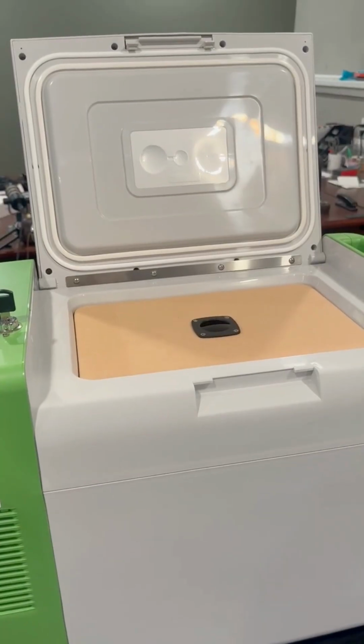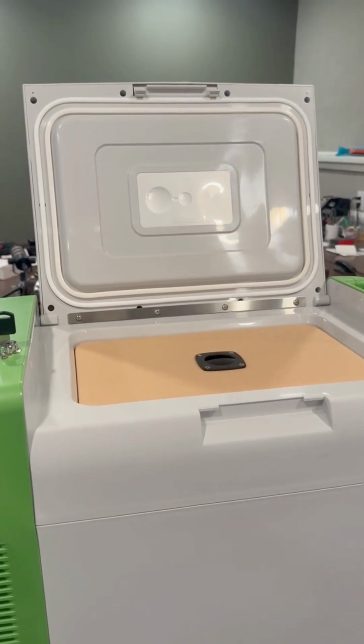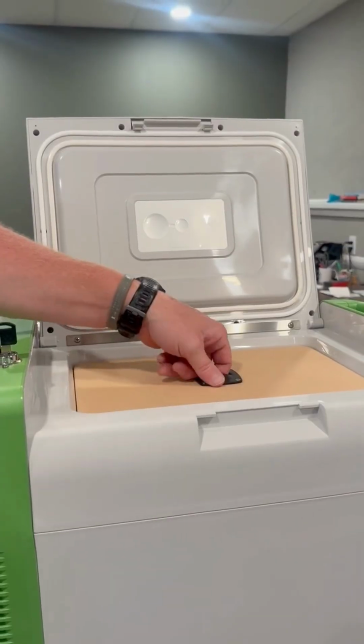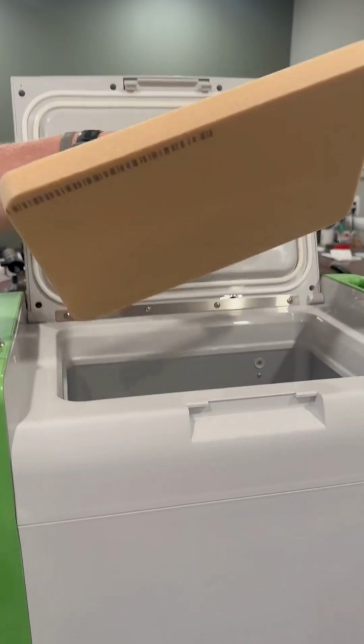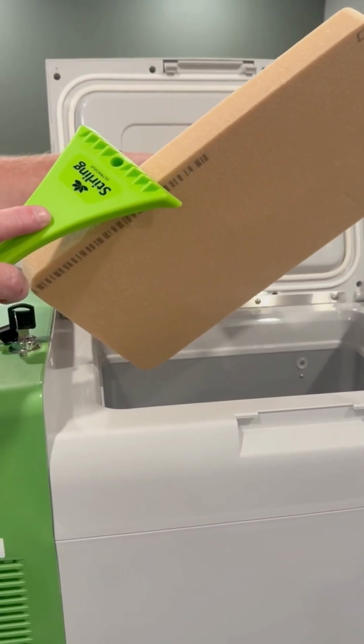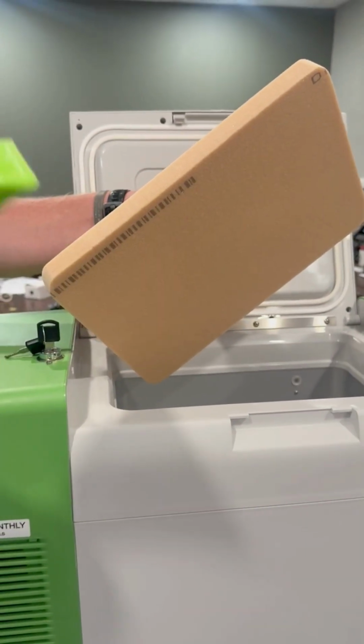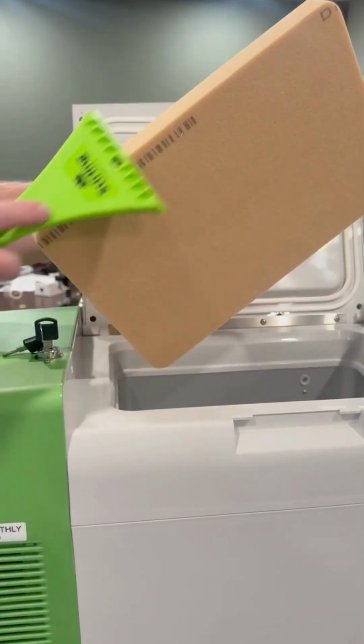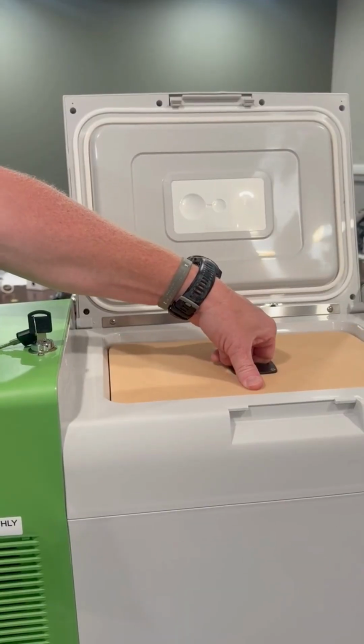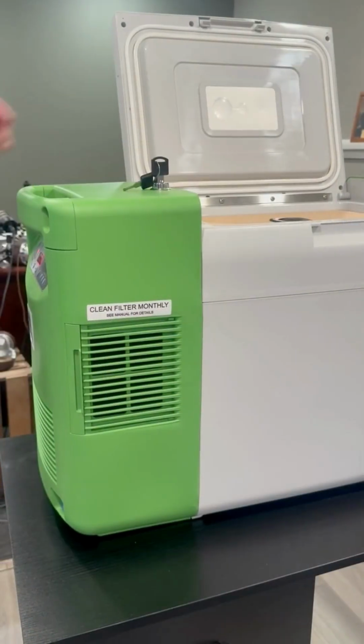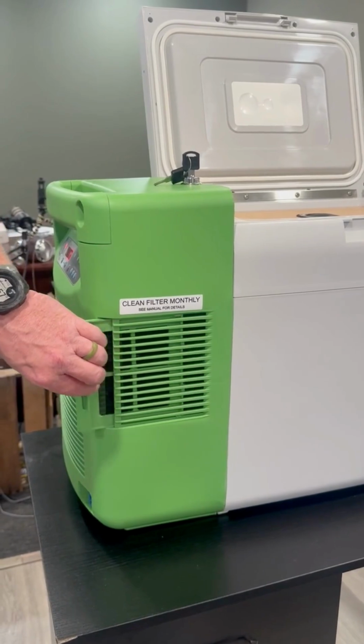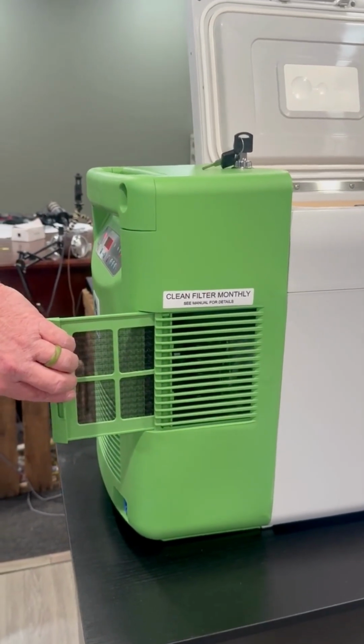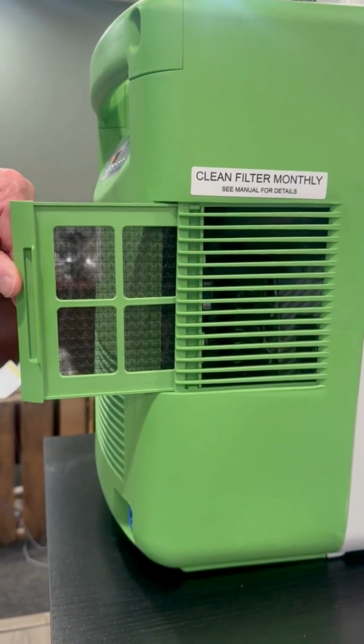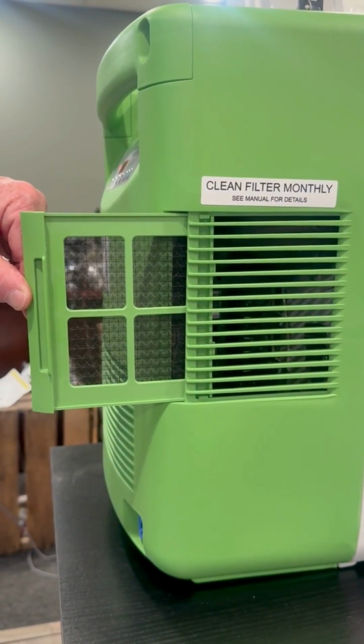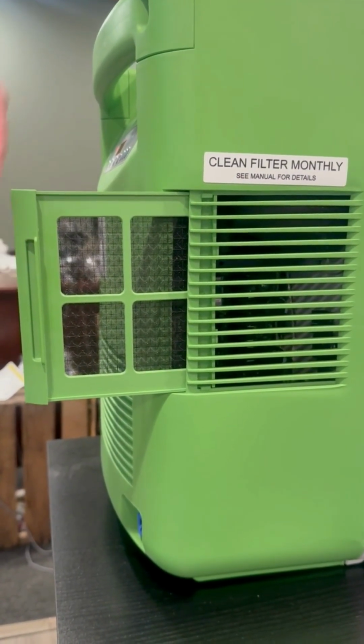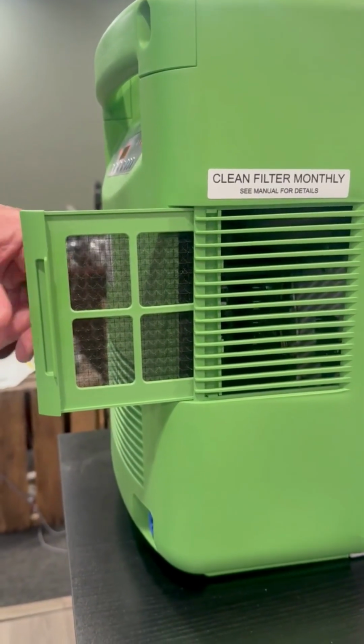The ULT25 is a very special freezer in its ability to only need a couple of maintenance items. The first maintenance item is always once a month. We recommend that you check your foam lid for ice buildup. If you do have ice buildup, simply take an ice scraper and gently scrape the sides to allow for a nice seal inside the cabinet. The second maintenance item we recommend monthly is the unit's side air filter. You can either use dust off or a vacuum cleaner. We recommend a vacuum because if you use dust off, it could blow and then just be sucked right back into the unit.